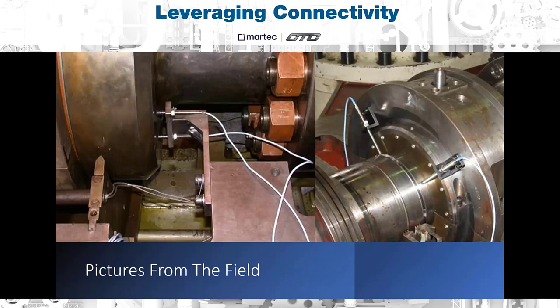So what differentiates CTC from much of the industry that manufactures these probes is we only have a 10 business day lead time on all of our proximity probe systems, regardless of quantity. And they are directly compatible with all of the major manufacturers of rack systems, machine protection systems, and online software. All of our proximity probes comply with API 670 standards, which is the industry standard governing all proximity probes used for predictive maintenance applications.